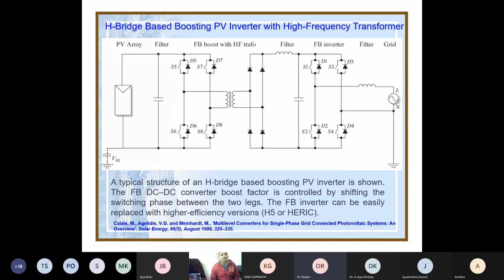So this is our PV array. You can see a filter and then a boost with a high frequency transformer. Last time when we discussed the dual active bridge converter, we studied that for a 1 kVA transformer, the size is simple, only 5 centimeter to 5 centimeter, whereas an actual 1 kVA transformer is very large. So going high frequency means component size reduces drastically.